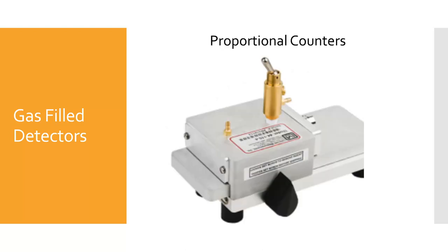Proportional counters are another type of gas-filled detector. This device uses a similar process to the Geiger-Mueller tube in that once the electron is ejected, it propels other electrons out of their shells through a chain reaction, called the cascade effect. The proportional counter can distinguish between alpha and beta radiation and is used to assess small amounts of radiation.